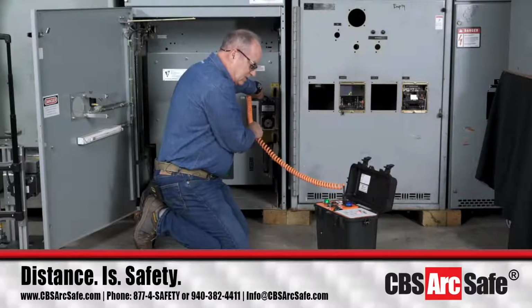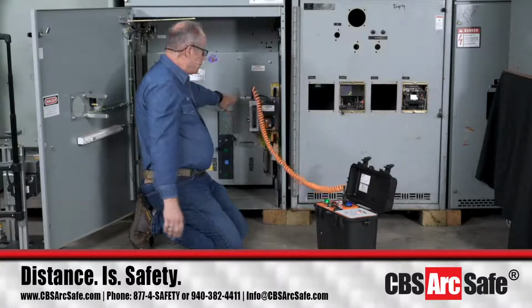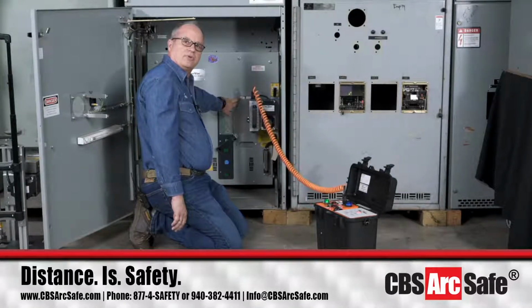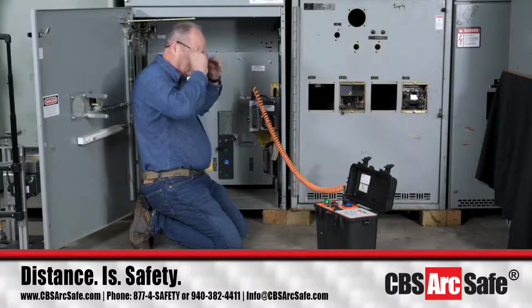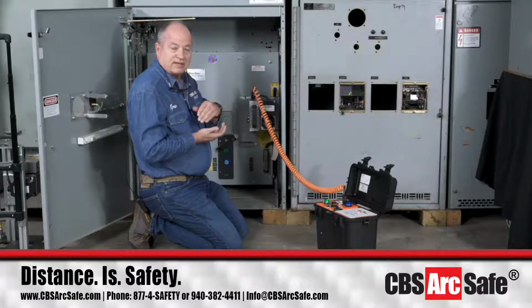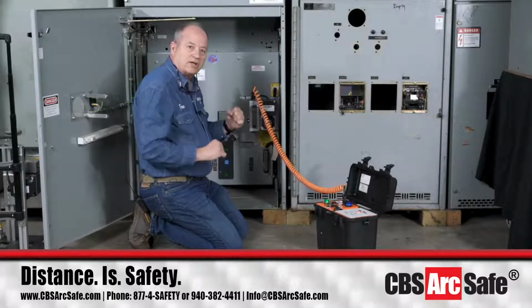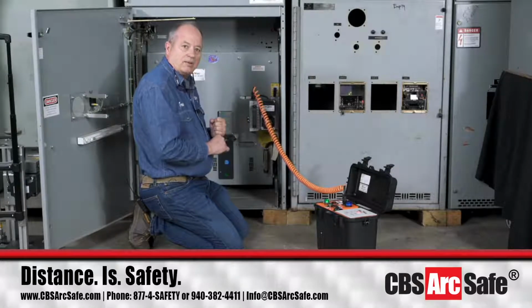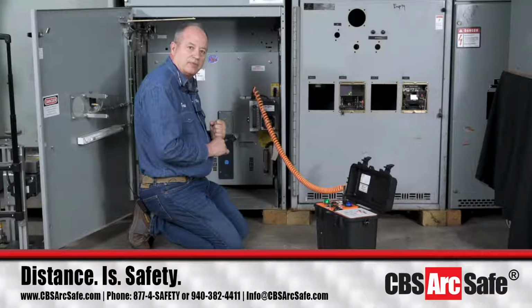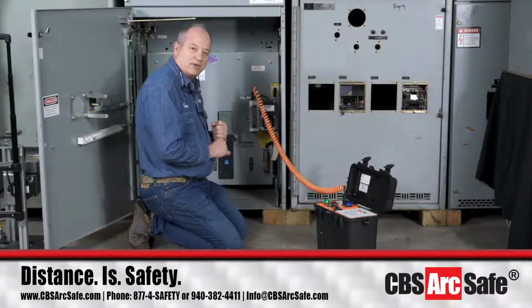One thing I want to point out is you have your breaker connected indicator—it shows test, disconnect, and breaker connected. If you have wear and tear in this racking mechanism, as I found in a demonstration the first year, I could tell because the word 'connected' wasn't centered in the picture, meaning the breaker wasn't going to operate properly. I had to help the operators in a power plant figure that out, and once they saw it was a wear and tear issue in their breaker, they learned that maintenance is something that appears in different ways.